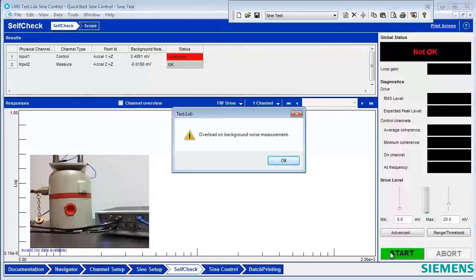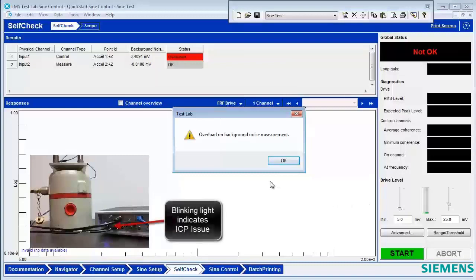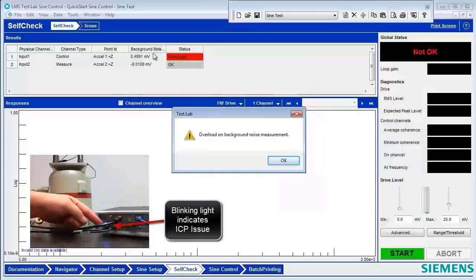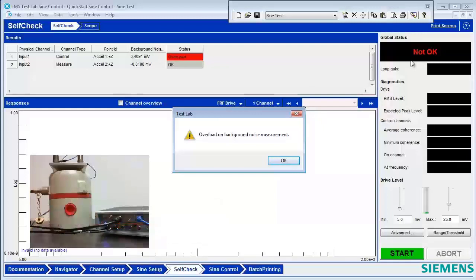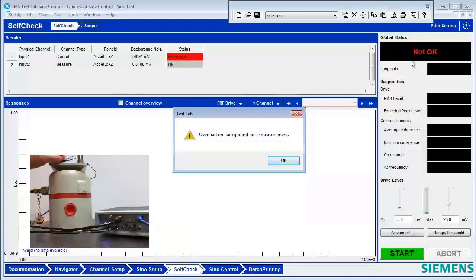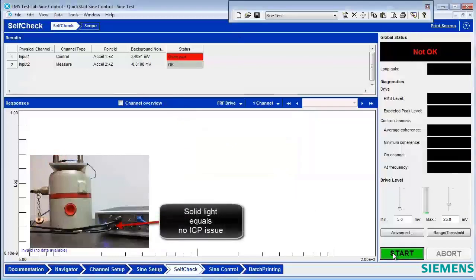And this time, we got an overload indication right away, before the broadband level was even sent out. The overload indicates that there's a condition on the first channel. Probably the ICP power is not being supplied properly. The current draw is not correct. This is due to a loose wire, and so now we'll tighten the wire on the control channel, and rerun the test.